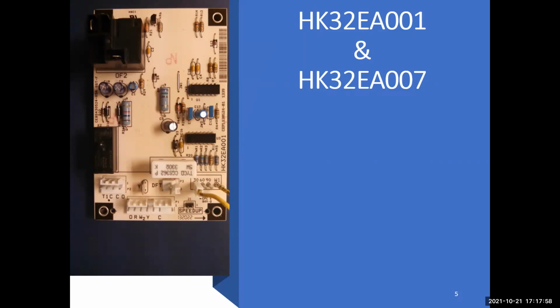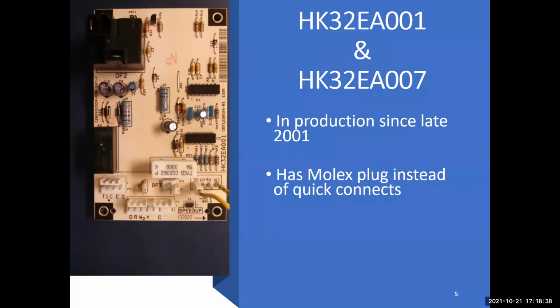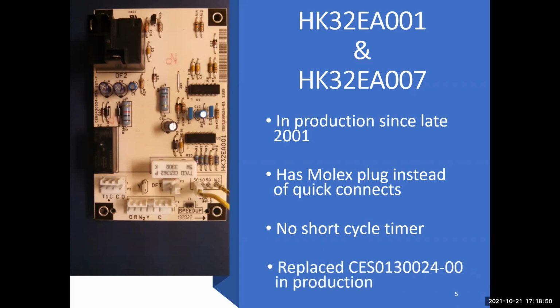The control is designed to operate with a Y call to the compressor contactor. The defrost timer accumulates the compressor runtime on a Y input signal. This control also requires a 24-volt signal to R and C terminals to power the control timer and the output functions. The reversing valve function is also routed through the control on O circuit. It was introduced in late 2001. It has a Molex plug instead of the old quick connects. There is no short cycle timer, so that's a compressor timer. And it replaces the old CES0130024-00 from production.